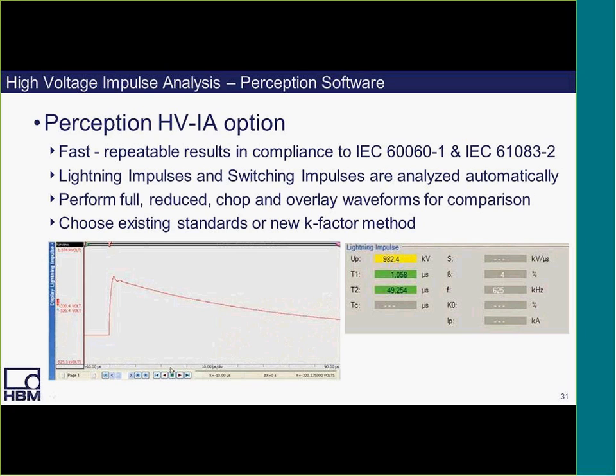In fact, lightning impulses with either overshoot, oscillation, chopping, or a combination of the three are analyzed without user interaction, and waveforms can also be overlaid for comparison, for example, full and reduced, to determine any changes in their characteristics. Now, there's also integrated pass-fail indicators with user-definable limits, which increase testing throughput and productivity, and you can also choose to use the existing standards or the new K-factor method.